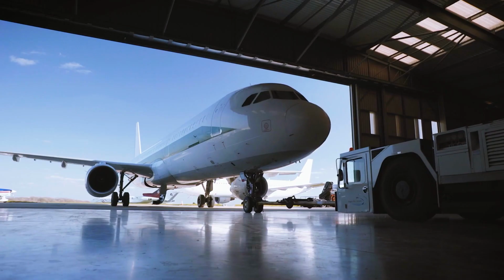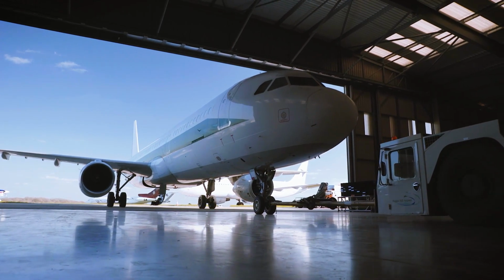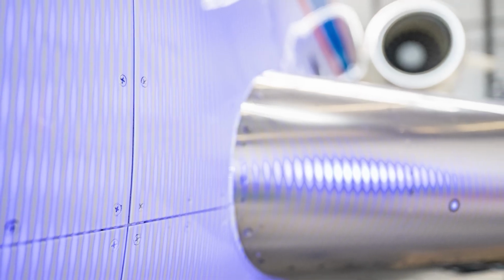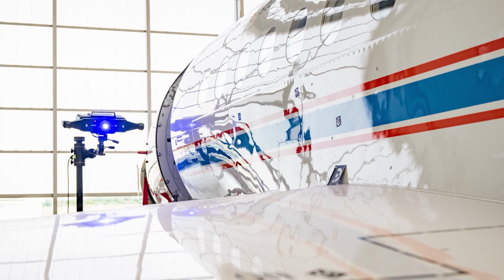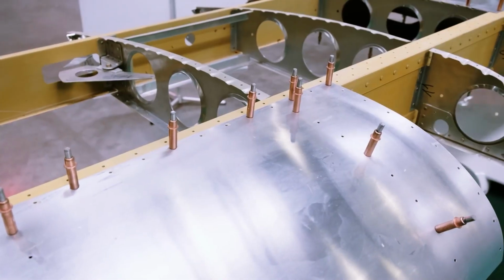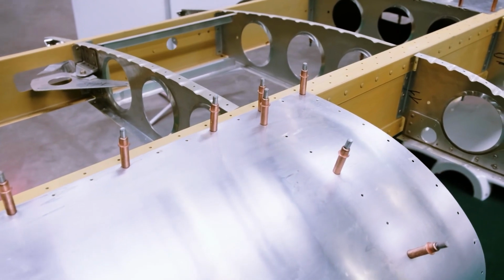I'm excited for the new addition to our portfolio, the Atos LRX. In aerospace, we have very large objects, fuselage, wings, where the Atos LRX, with its very short measurement time, will really enhance what we can do with 3D data to support the needs of the aerospace industry. I expect to see the sensor used in manufacturing and assembly of aerospace components, both in a manual and in an automated way. In particular, I feel the fuselage, especially in its green state, looking for the shape, profile, form, and especially defects prior to paint, which can be really costly to rectify.